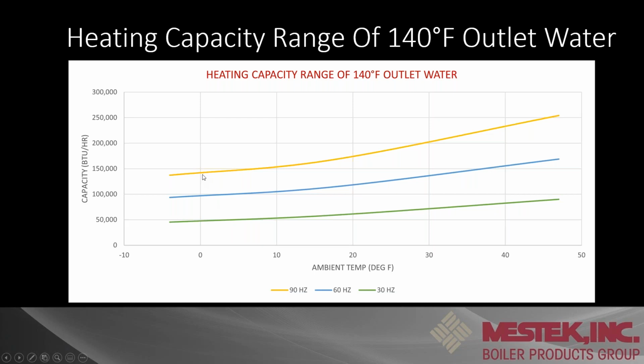The reason I'm showing these charts to you, and this is all in our submittal data as well, is that when we're designing a system, after we do our load calcs and have the bin data for that particular area, we want to make sure we're sizing these units accordingly for worst case situations. And if we don't want to size them for worst case, let's say I want to run this heat pump down to 20 degrees outside, and anything below that I want a boiler to kick in. You can do that as well to try to get your maximum efficiency and the water temps you need coming out.